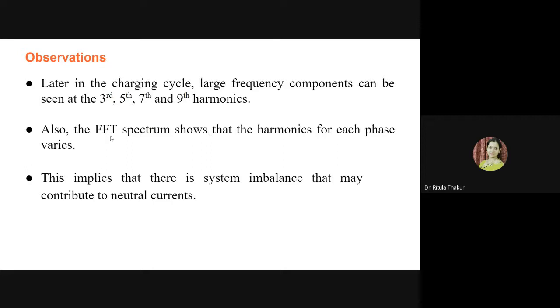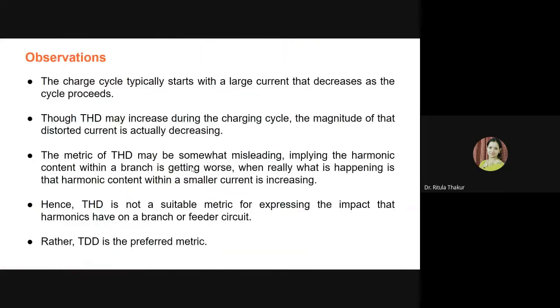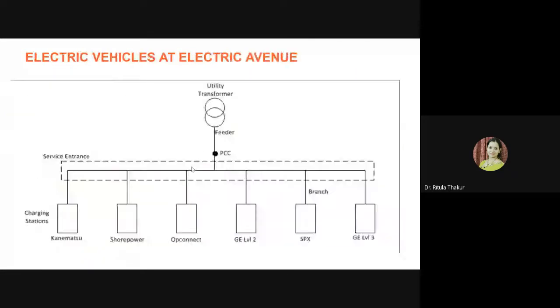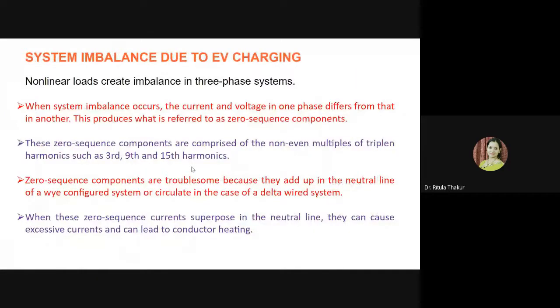Also, we can see that the harmonics of each phase also vary. I couldn't put the FFT spectrum figure here, but there was an FFT spectrum which showed that even in each phase, the harmonics differed. So what does it mean? It means that there is system imbalance that may contribute to the neutral current. This is what I told you in the slide initially, when we were talking about the system imbalance due to EV charging.